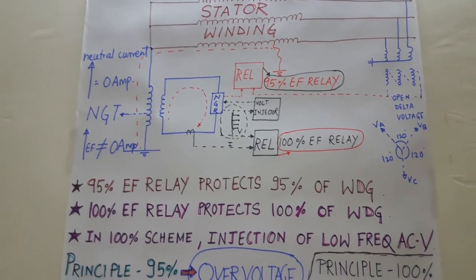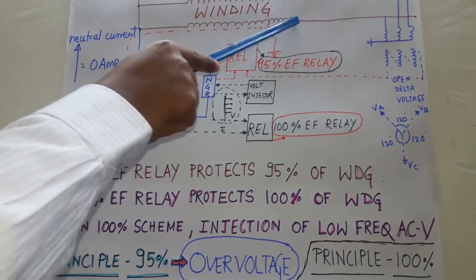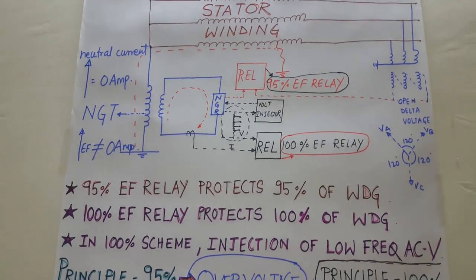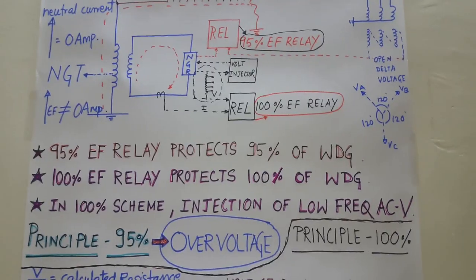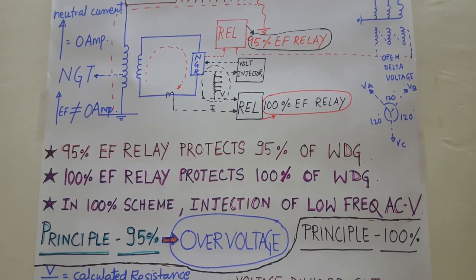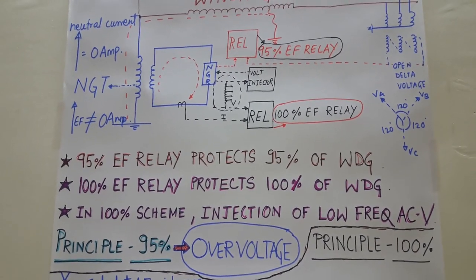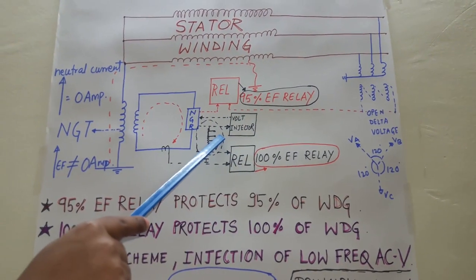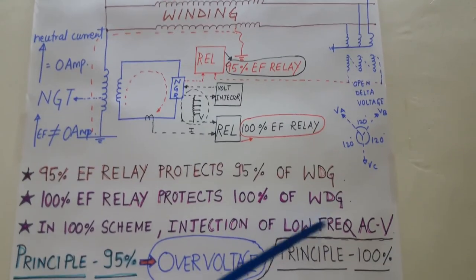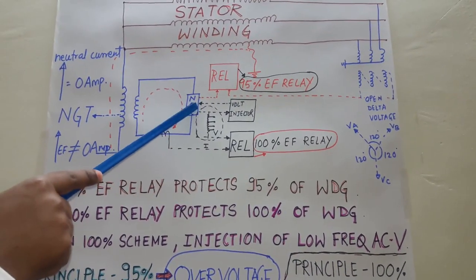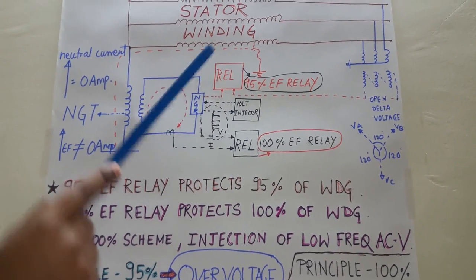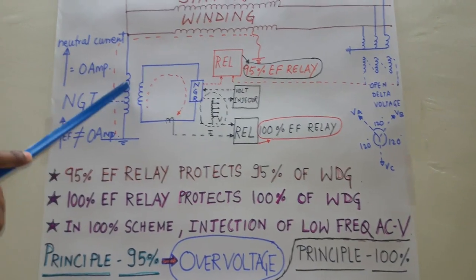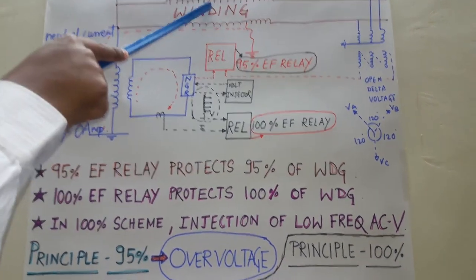So we have to provide one more extra scheme for protecting the entire 100% winding. This scheme is also known as the voltage injection principle. In the voltage injection principle, we have a voltage injector. This voltage injector injects a low frequency signal into the NGR — a low frequency AC voltage. This low frequency voltage is passed to the NGT primary and from there it is passed to the stator winding.